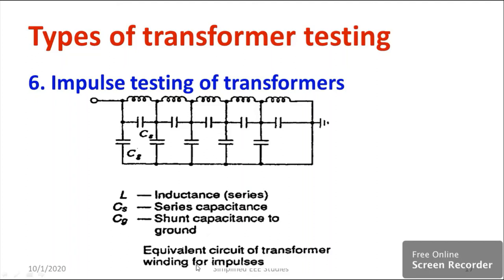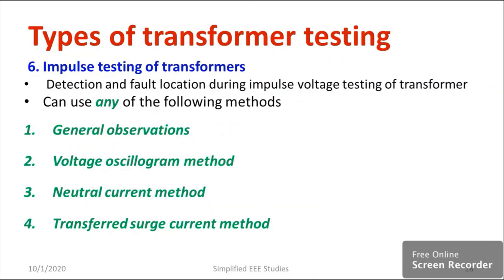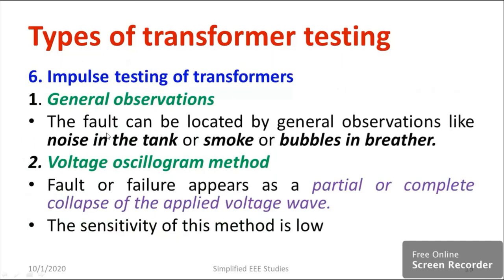These are the equivalent circuit components of the transformer winding for impulse testing. There are different procedures for conducting impulse testing, and an impulse generator is mandatory. The checklist of various procedures includes: number one, general observation; number two, voltage oscillogram method; number three, neutral current method; and finally, transfer surge current method.